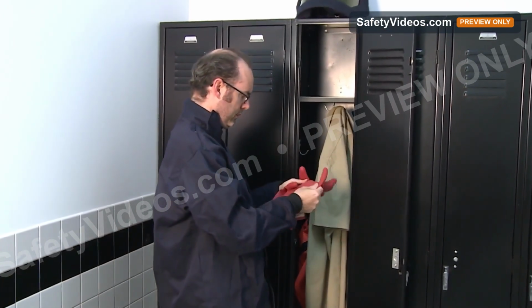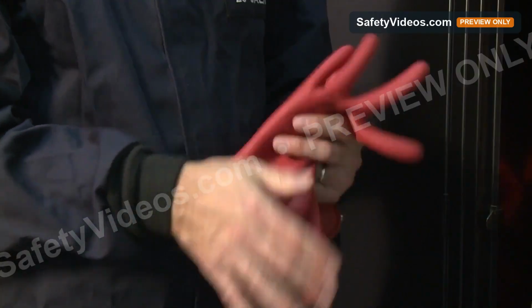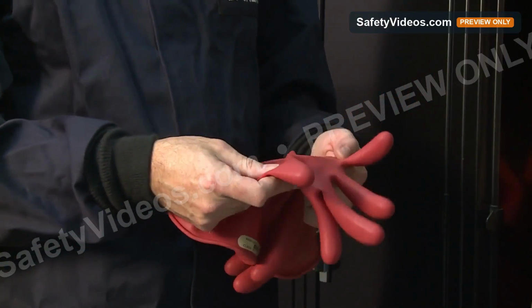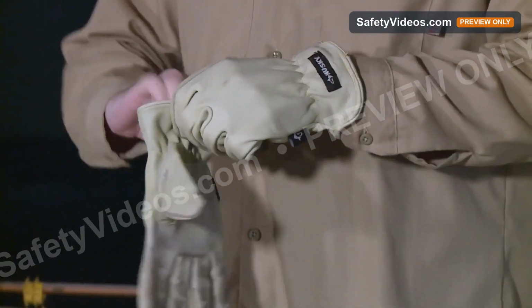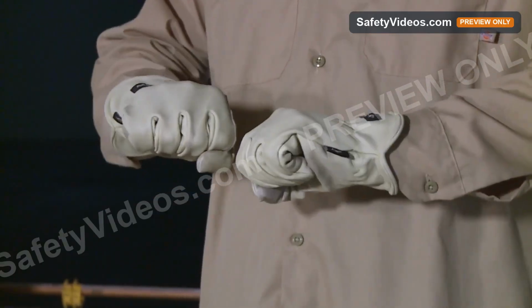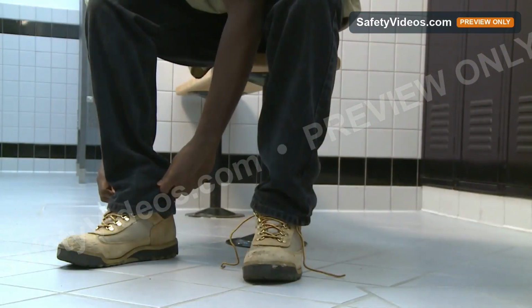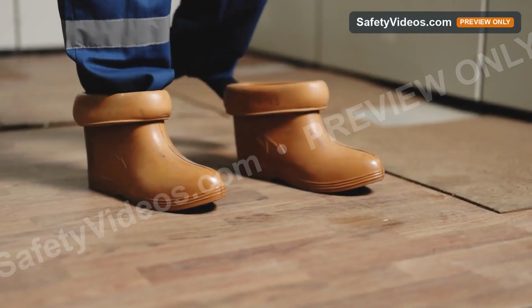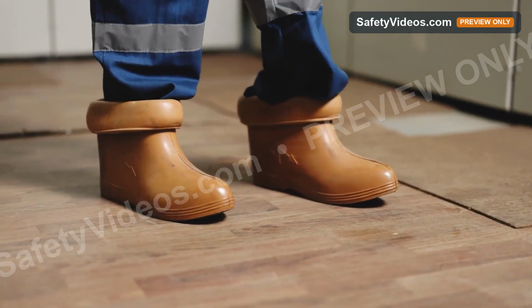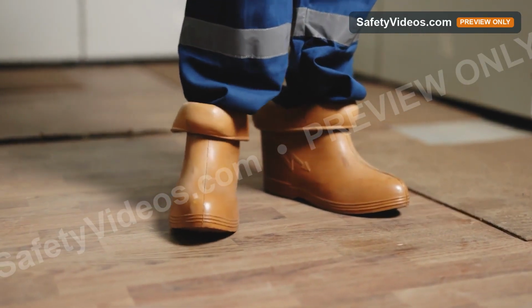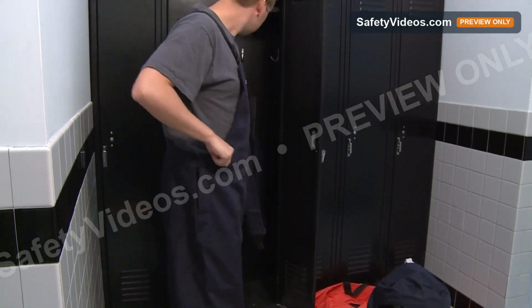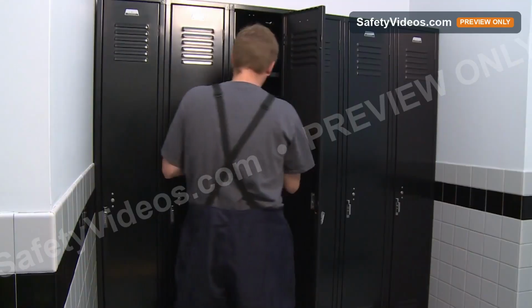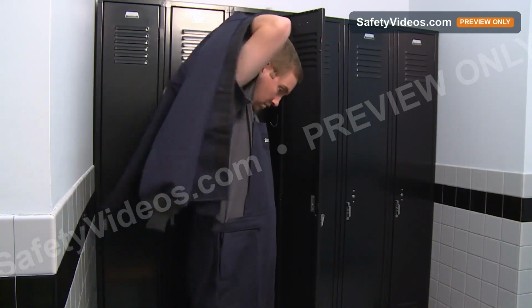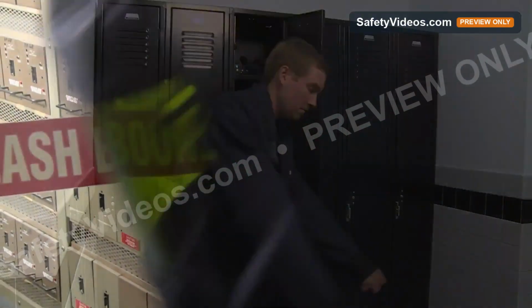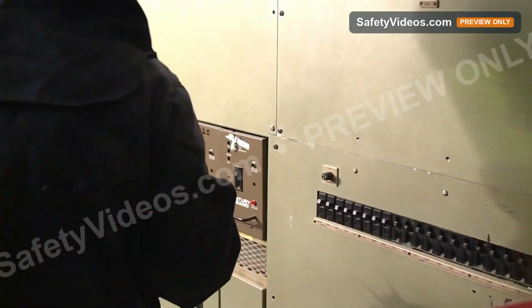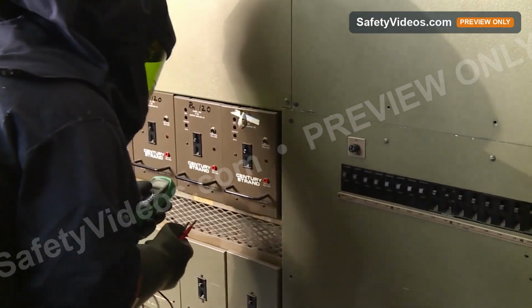To avoid an electric shock to your arms and hands, you need to wear rubber insulating gloves and sleeves with protectors. To guard against an arc flash, heavy-duty arc-rated leather gloves are best. And don't forget about your feet. Insulated or leather footwear can provide protection against electric shock and arc flash events as well. As for the rest of your body, you should wear arc-rated clothing, such as an arc flash suit, to protect yourself against thermal burns when you are within the arc flash boundary of the equipment you're working on or using.